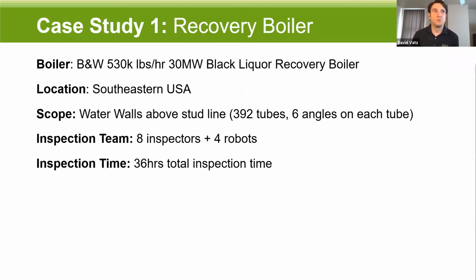All right, we'll hop into some of the case studies here. First, we're going to go over a recovery boiler that we did down in the Southeast, where we scanned all of the water walls above the stud line. We performed this inspection in about 36 hours total.